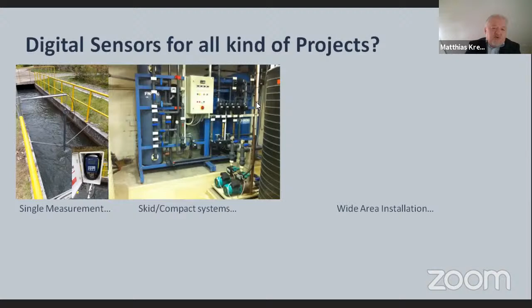For all these installations, digital sensors have advantages: simple plug-and-play installation, secure data transmission, and transmission of additional sensor data like lifetime, calibration, logbooks, min-max values, and so on. We can have remote access to the sensor once it's digitalized, and we can network sensors with actuators, pumps, and valves if necessary. This is the advantage of digitalizing analog sensors.